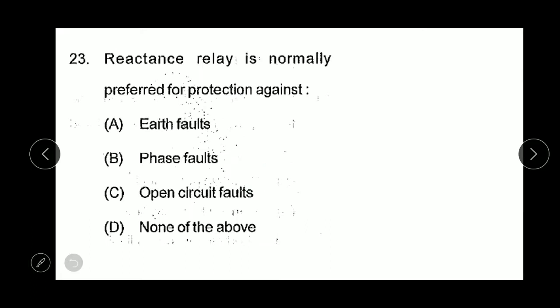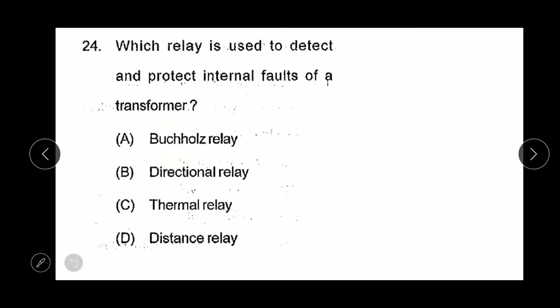Next question: reactance relay is normally preferred for protection against earth fault, because reactance relay is not affected by variable impedances. Earth fault is generally associated with variable impedances which generally do not affect the reactance relay. Which relay is used to detect and protect internal faults of a transformer? This is Buchholz relay.